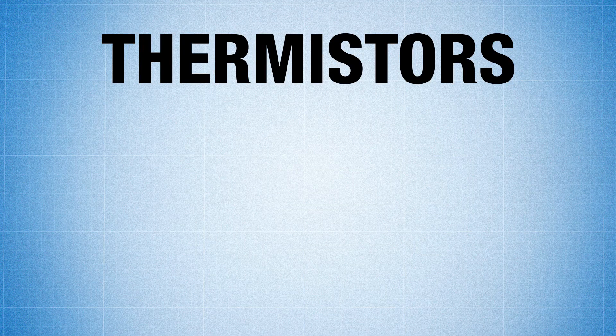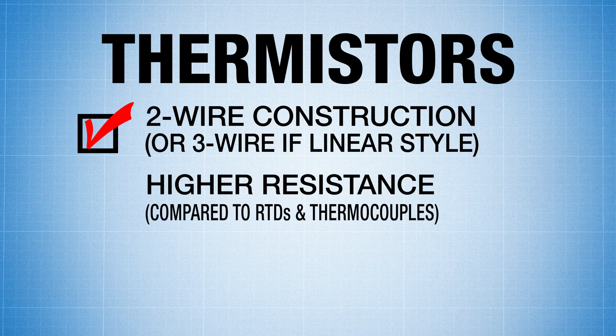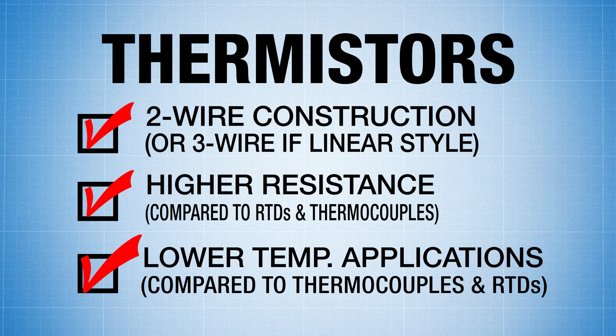Finally, thermistors. They usually come in a two-wire construction unless they're linear where they'll have three wires. They have a higher resistance compared to RTDs and thermocouples and are generally used in lower temperature applications compared to thermocouples and RTDs.